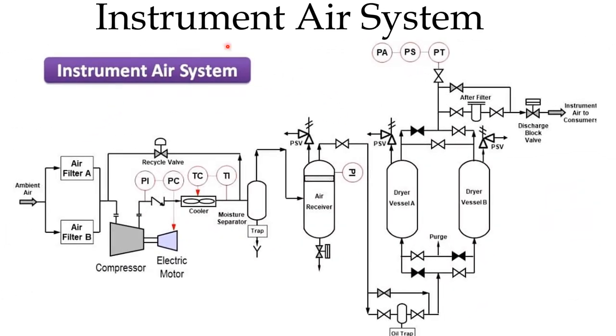This is the schematic diagram of the instrument air system used in offshore, marine facilities and small capacity plants. It is a package type compressor. Ambient or atmospheric air is drawn through filters entering the compressor. Compressor discharge through NRV is cooled in the air cooler. Moisture is separated in the moisture trap. This is the recycle valve to maintain the pressure. The air then goes to the plant air receiver or wet air receiver, which is provided with a pressure safety valve.